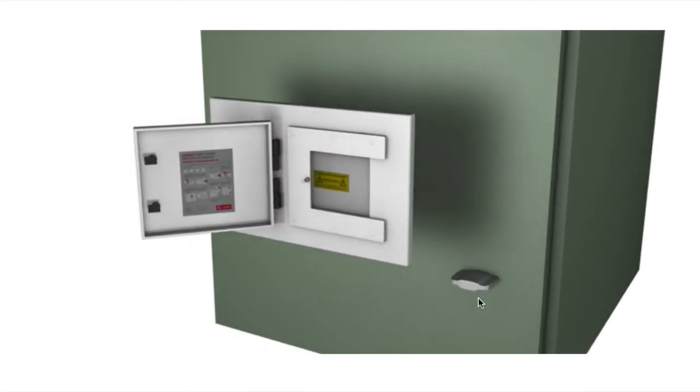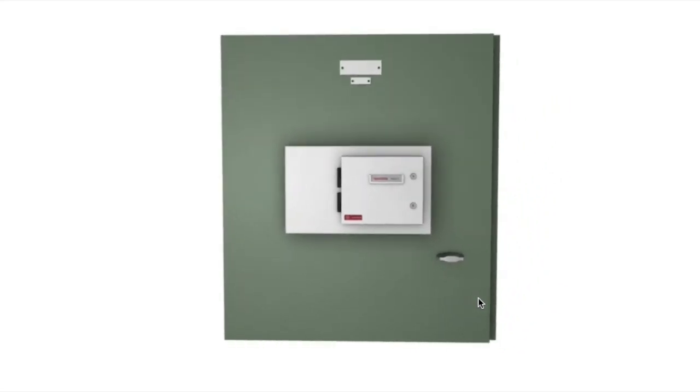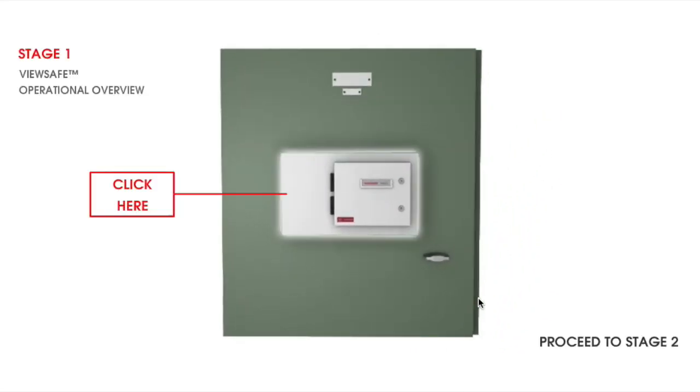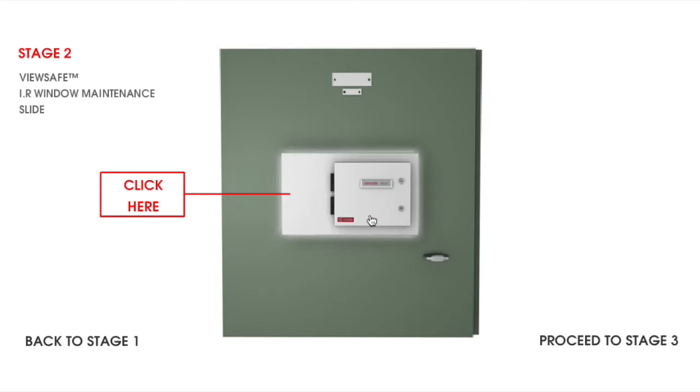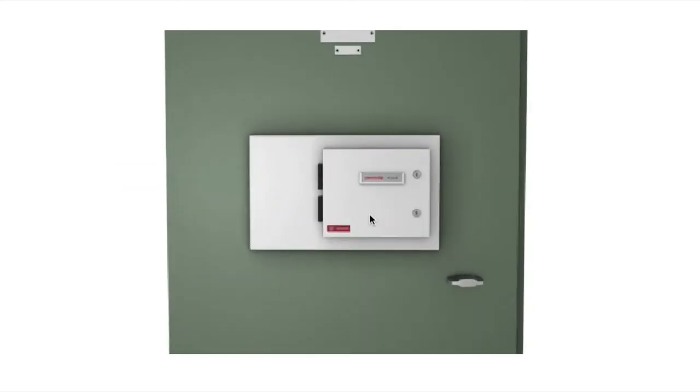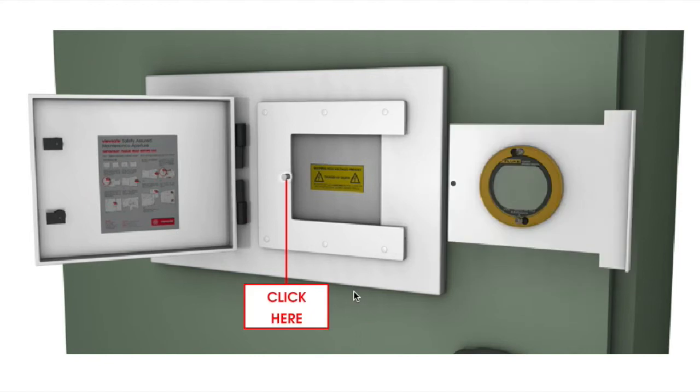With infrared thermography a proven method of inspecting electrical equipment, the ViewSafe IR window slide allows the operator to identify areas of insulation breakdown, loose connections, and areas of abnormally high resistance that would ultimately lead to asset failure.